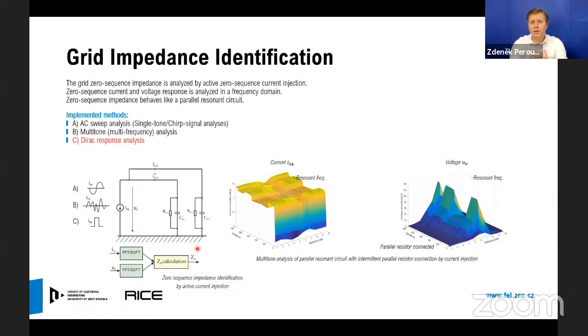We have a current source installed in the system. Our power electronics converter is able to generate a testing signal by which we are able to identify in real time the grid impedance. We implemented two possible techniques: multi-frequency analysis, and we have the best experience with the pseudo-Dirac response analysis. It means that we inject into the grid the pseudo-Dirac impulse. We know the current impulse, we know its frequency composition, and we measure the voltage response of the grid. We do the frequency analysis, and based on this frequency analysis, we can calculate the grid impedance in real time. And it makes it possible to calculate the necessary compensation current, which we are generating by our device.